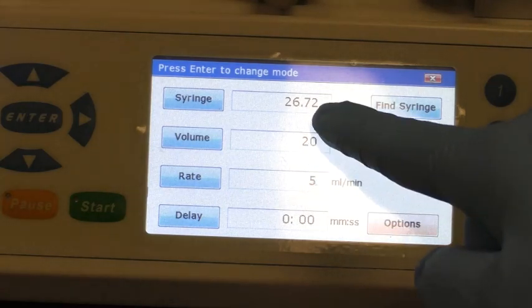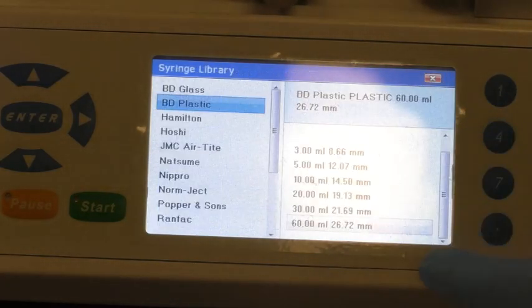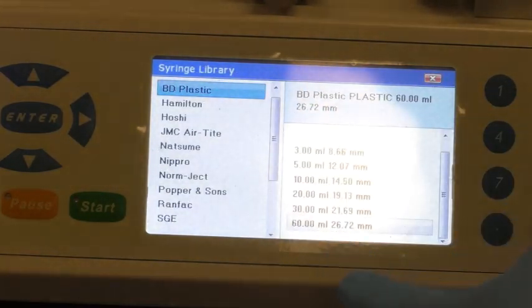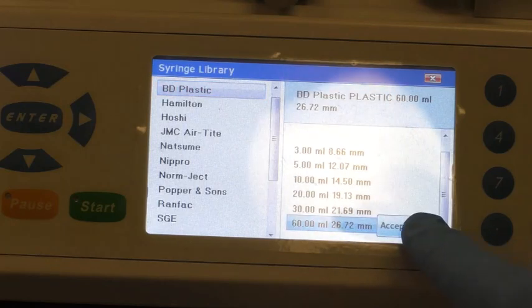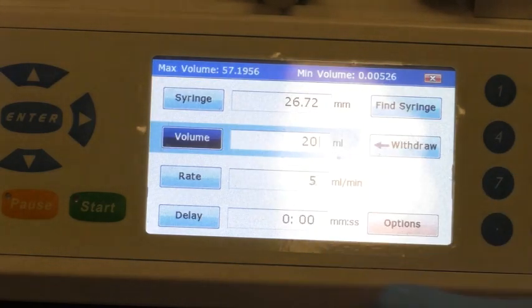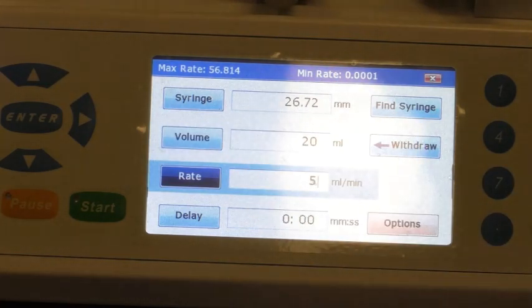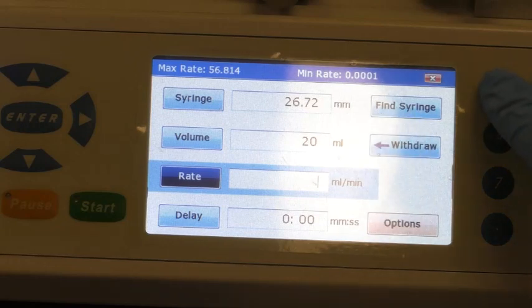On the syringe pump settings, you'll see a place where you can select your syringe. If the syringe is not correct, you can click on it and then search for the proper syringe. Today we are using a BD plastic 60 ml syringe, so that is what we will choose. Set the syringe pump to withdraw a volume of 20 ml at a rate of 5 ml per minute. While this is much faster than what you would use during cell culture, it is not fast enough to cause bubble formation.